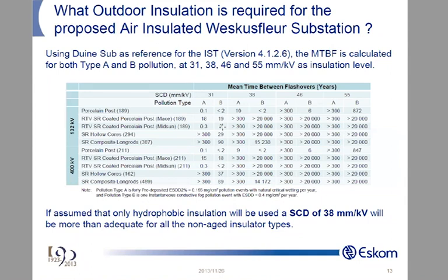And now how do you know which one to choose, and which one is performing better than the other? Get your pollution performance curves, use them, and make a decision. See the power of the tool, the power of the process. Now we go on, and we say if we use hollow cores, we'll get more than 300 years for the pre-deposit and 29 years for the instantaneous, and so on. And yet on the 400s, it's even better.